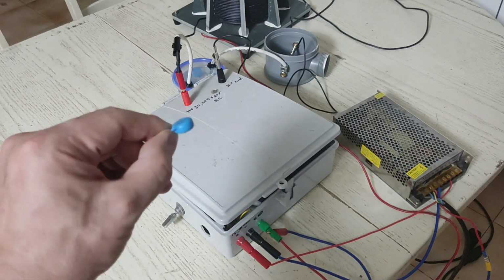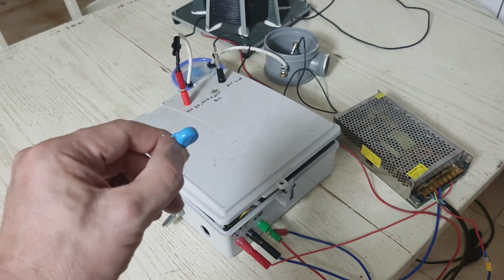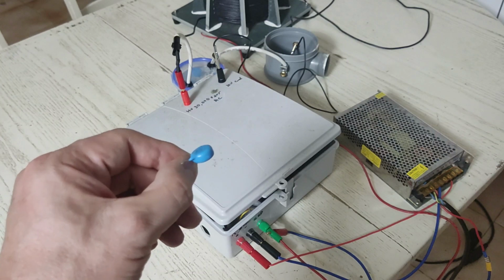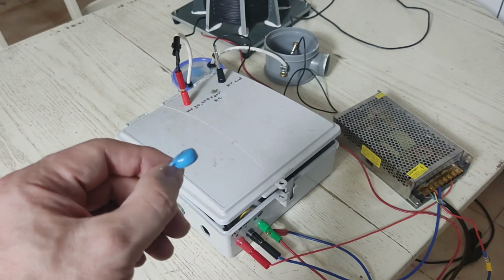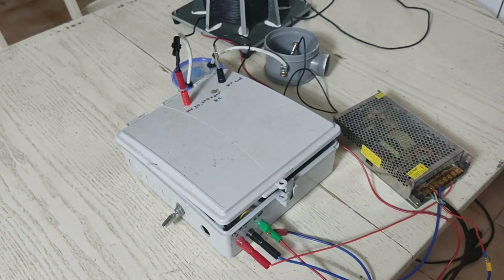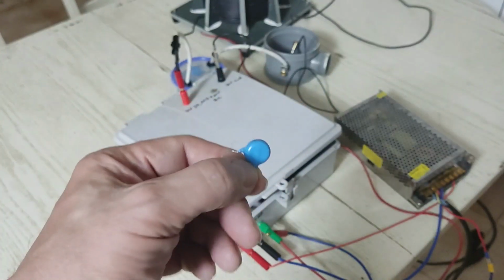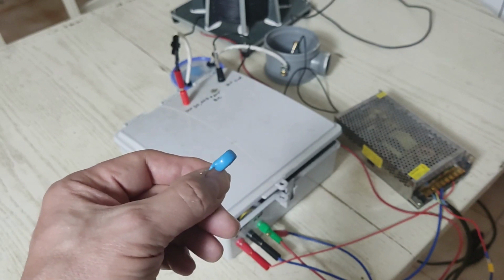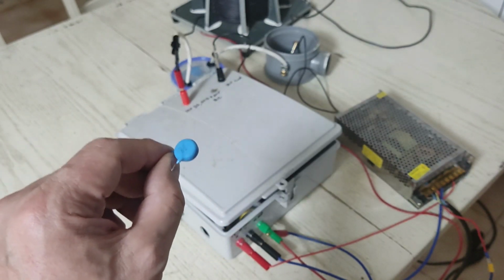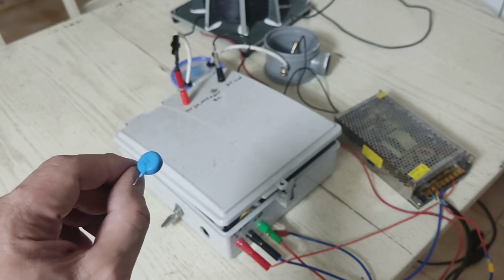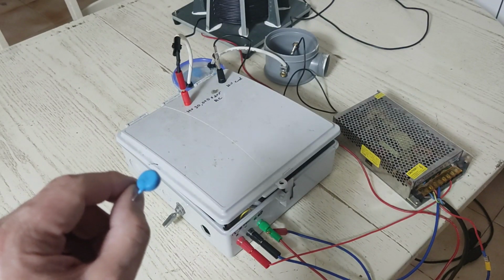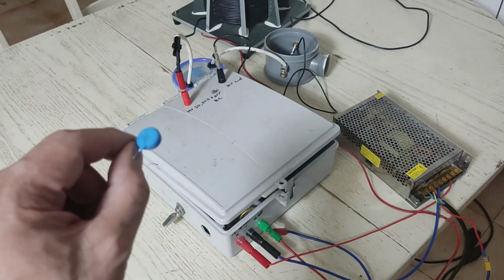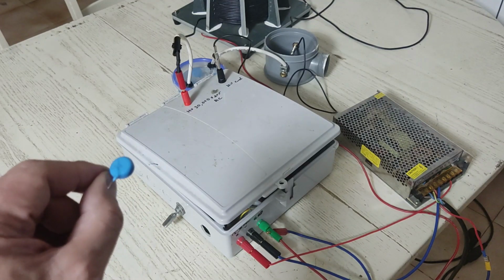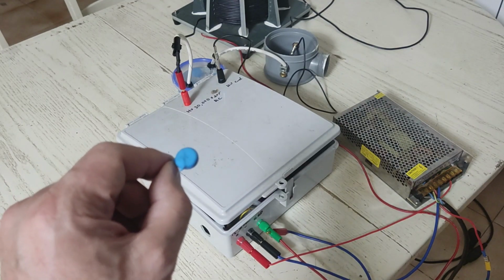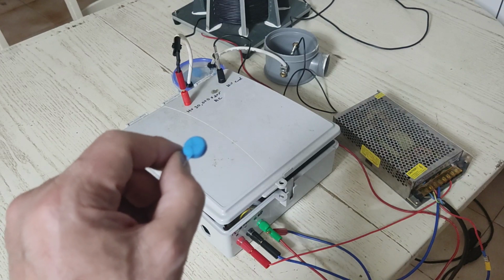I wouldn't consider using this because I need quite a few to get the capacitance I need, about 5 to 6 nanofarads, to make this work the way I have it set up. I could connect 5 together to get my 5 nanofarads, but you want more voltage rating on your capacitors than you're putting out, at least double. So if you're feeding in 20,000 volts, you want at least 40,000 volts on your capacitors to be safe, maybe more.